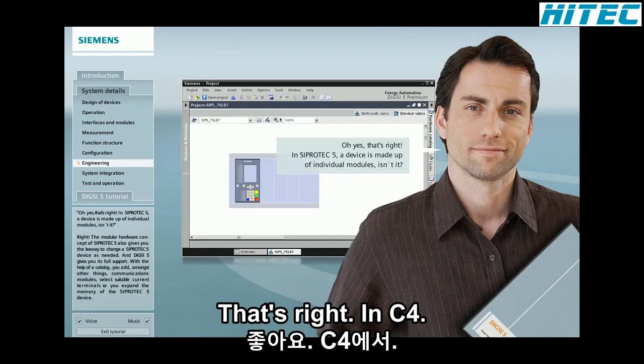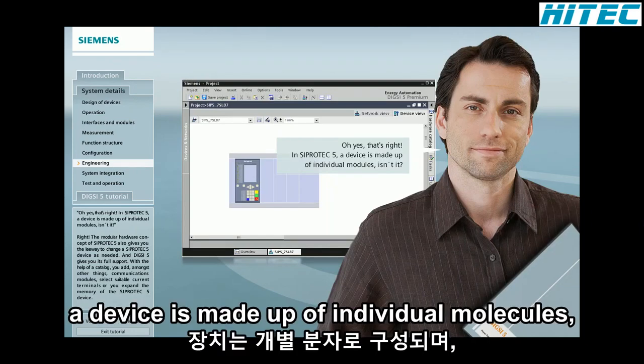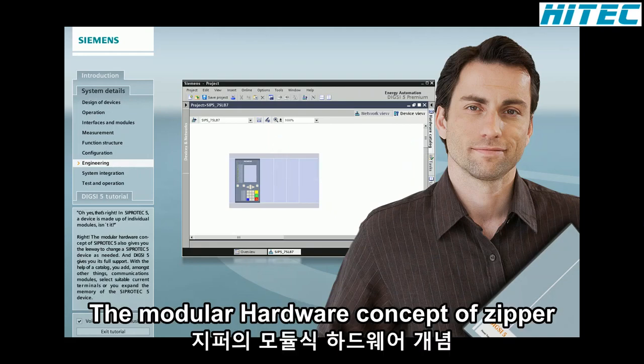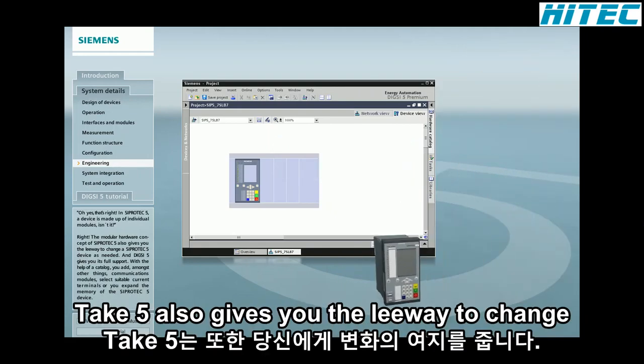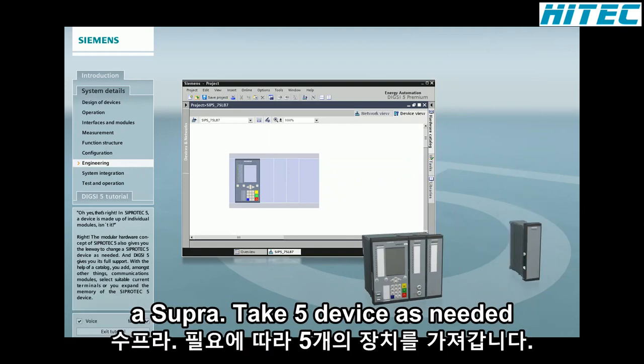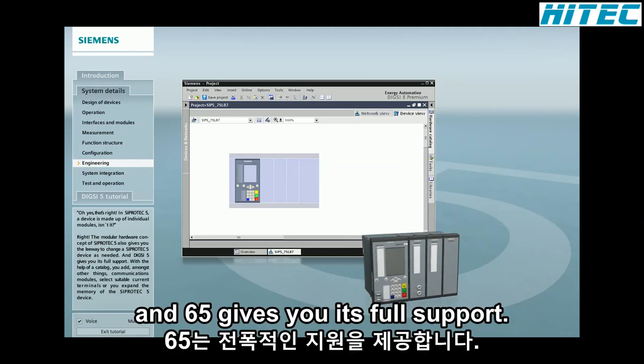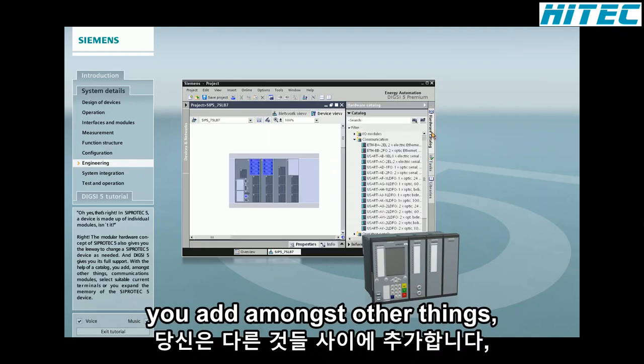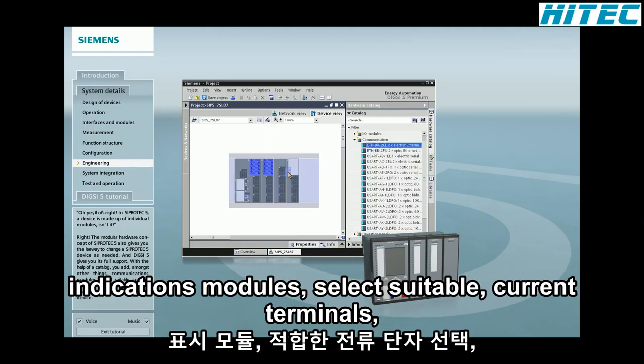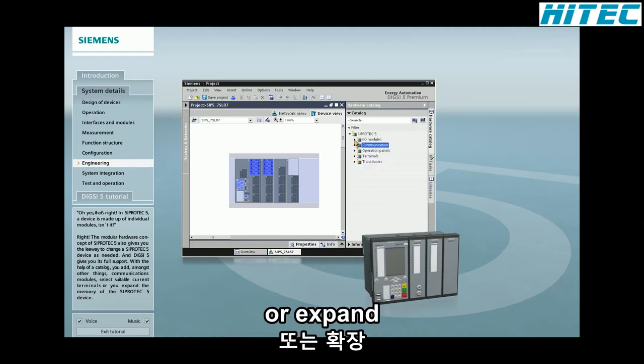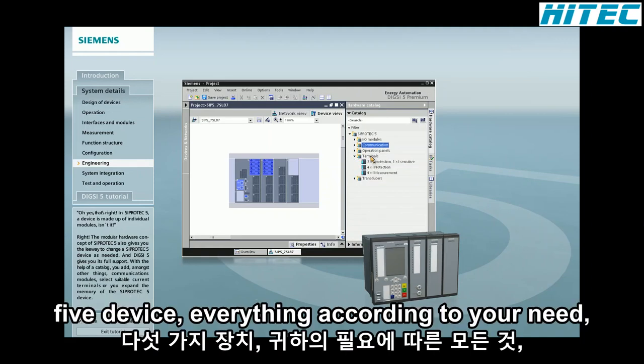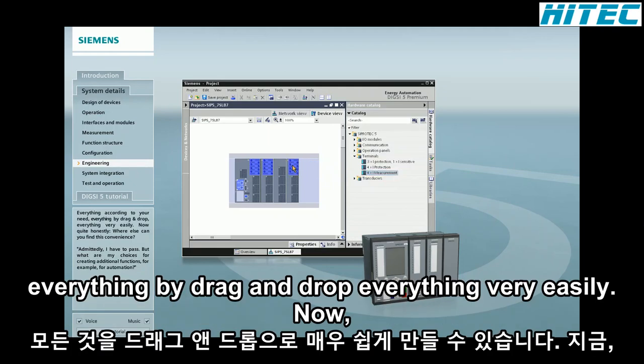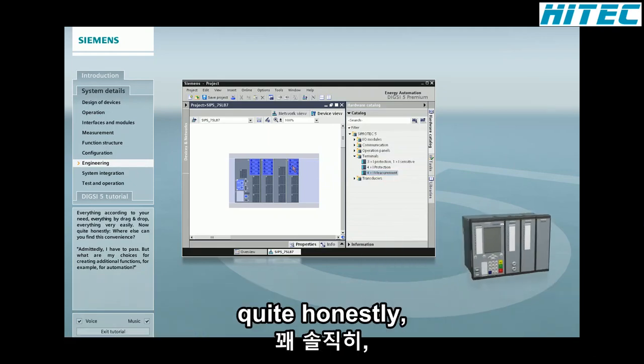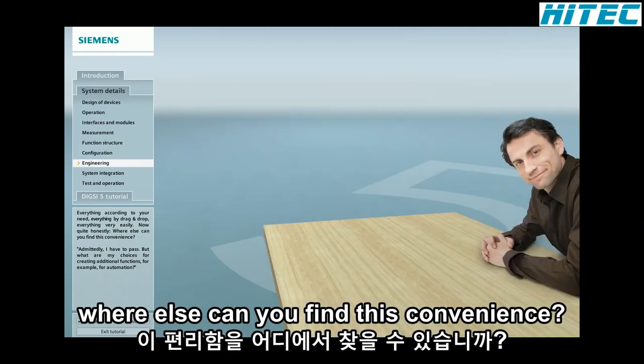Oh yes, that's right. In SIPROTEC 5, a device is made up of individual modules, isn't it? Right. The modular hardware concept of SIPROTEC 5 also gives you the leeway to change a SIPROTEC 5 device as needed. And DIGSI-5 gives you its full support. With the help of a catalog, you add, amongst other things, communications modules, select suitable current terminals, or expand the memory of the SIPROTEC 5 device. Everything according to your need, everything by drag and drop, everything very easily. Now, quite honestly, where else can you find this convenience?